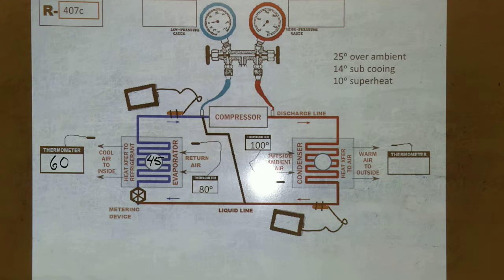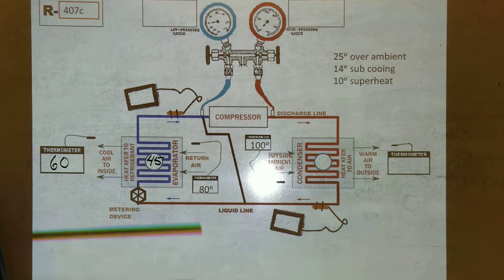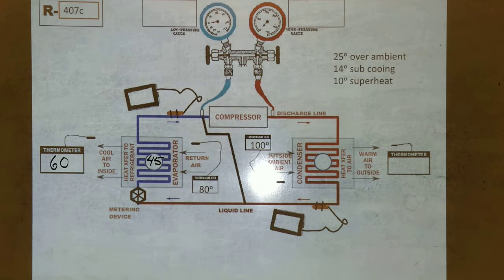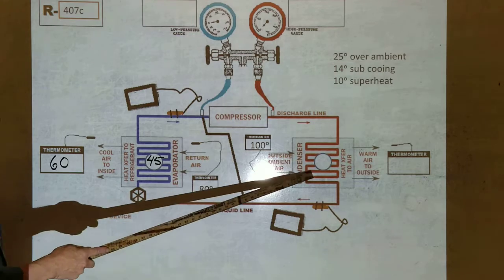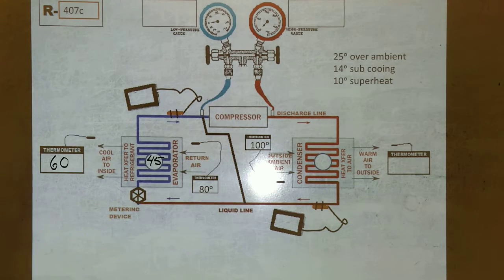Okay, and then on the other side, we'll move over here. It says 25 over ambient. What's our ambient temperature? 125? No, our ambient temperature is 100. So what's the temperature of our condenser? 125. So that's 125, right? Got that? Correct.